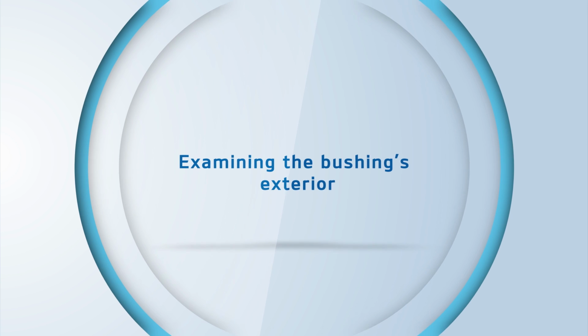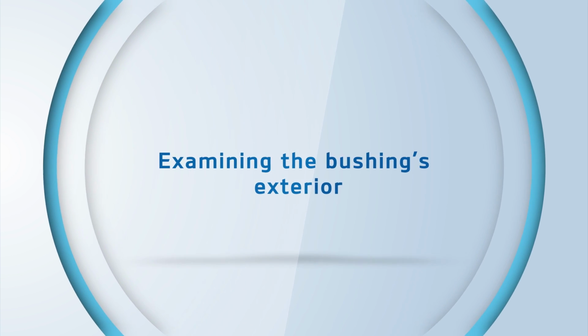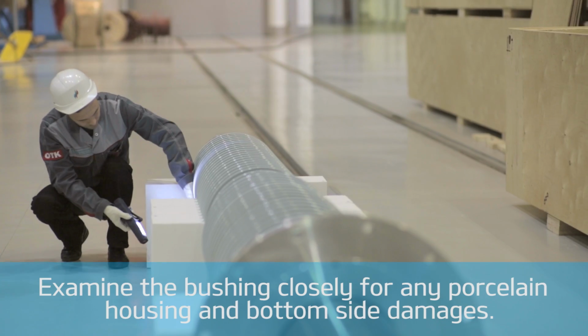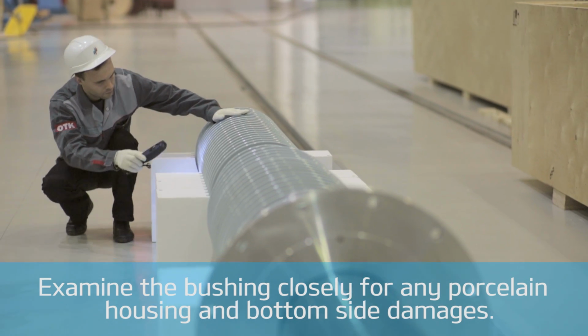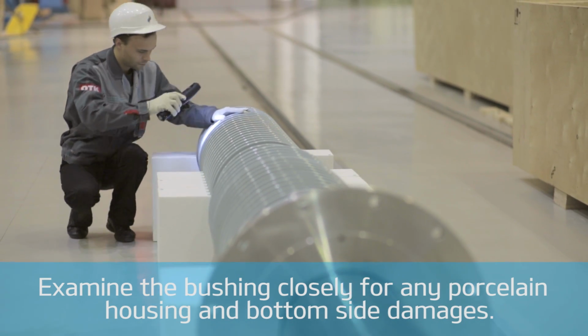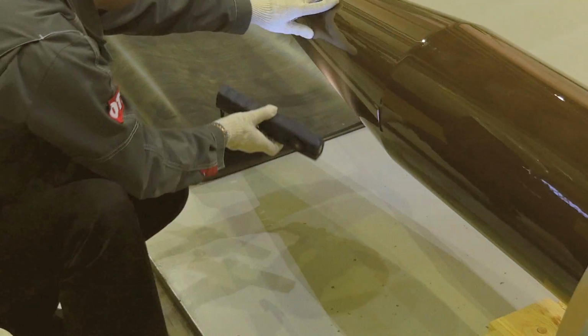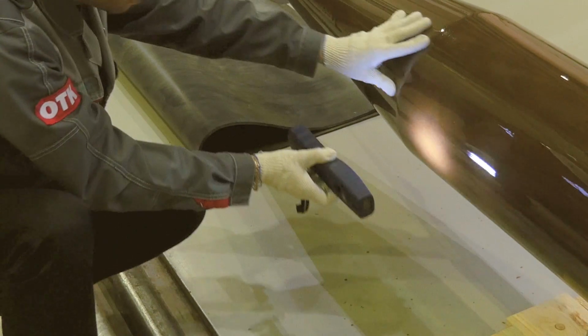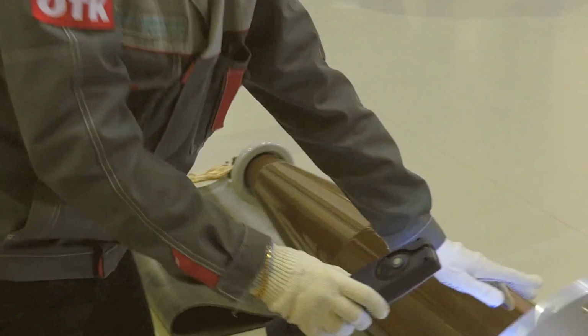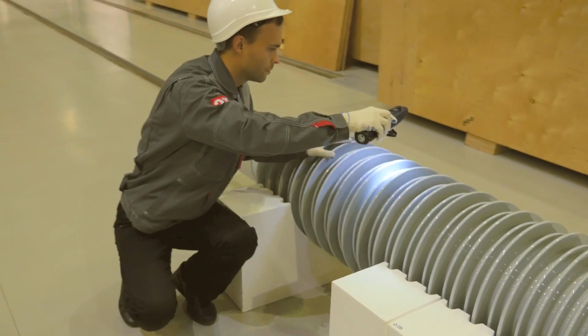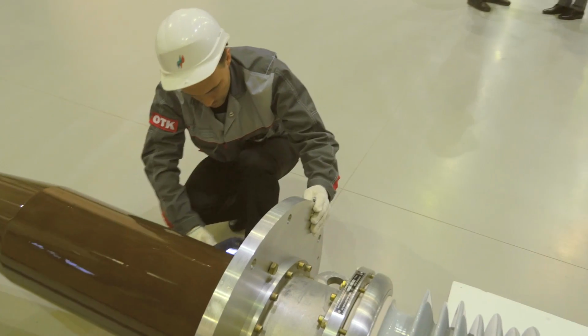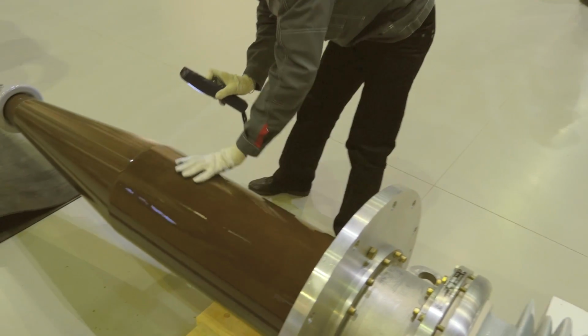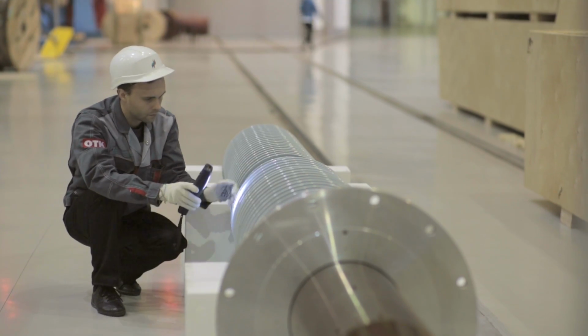Examining the bushing's exterior. Examine the bushing closely for any porcelain housing and bottom side damages. Pay special attention to any housing cleavages. None should be found, as they can develop later and fully destroy the housing, leading to the bushing failure. There mustn't be any oil leakages or damages on the parts of the bushing.